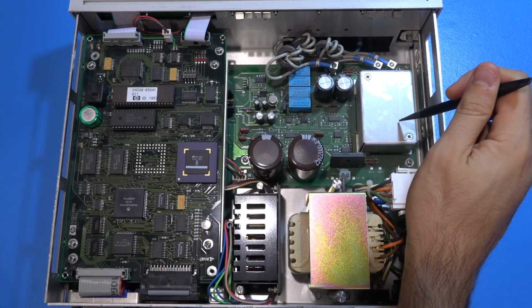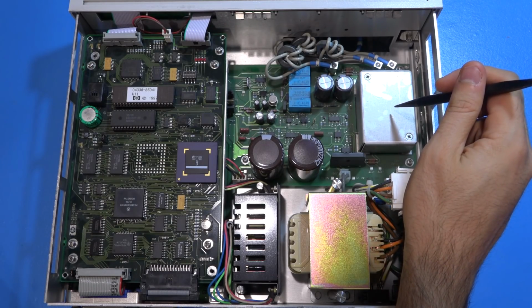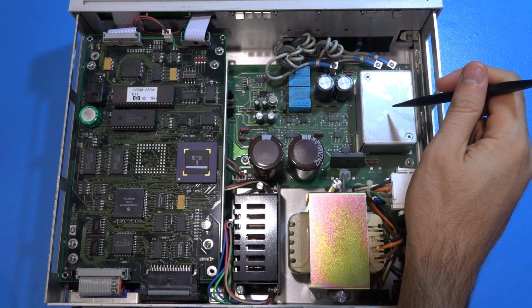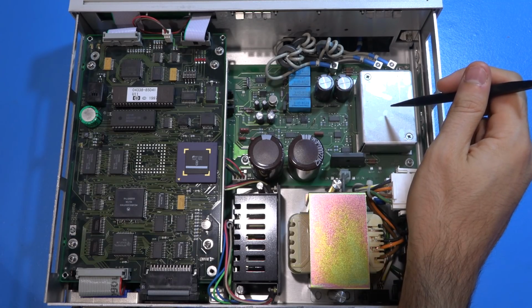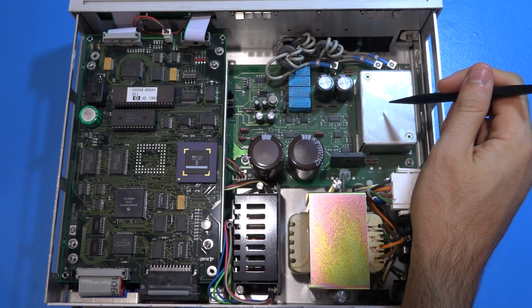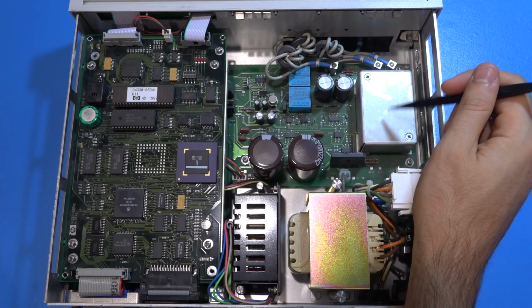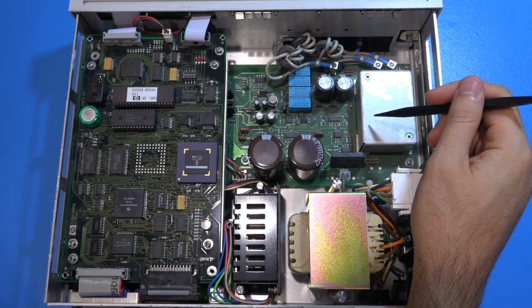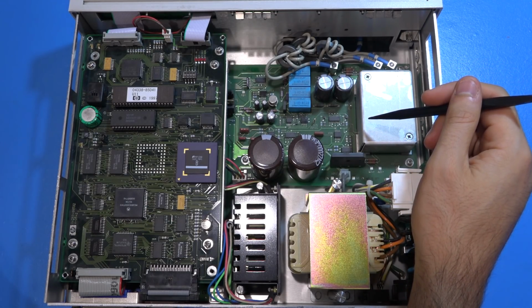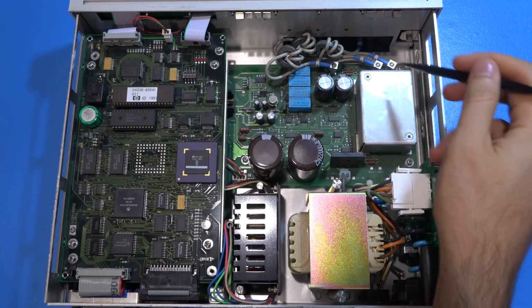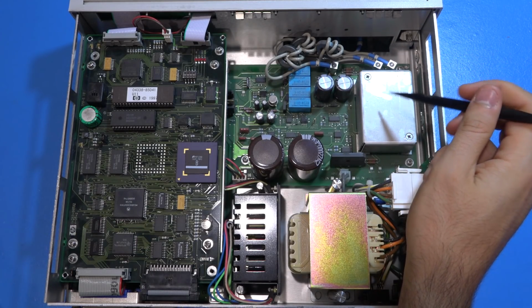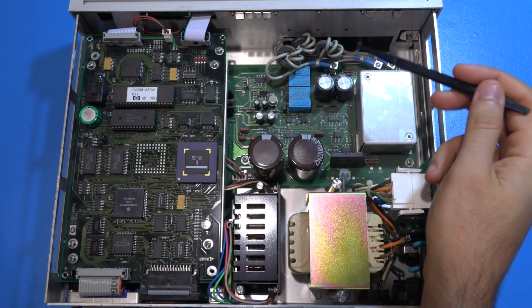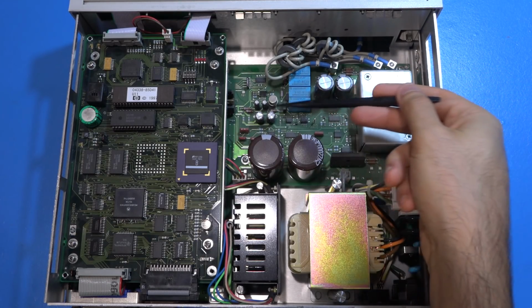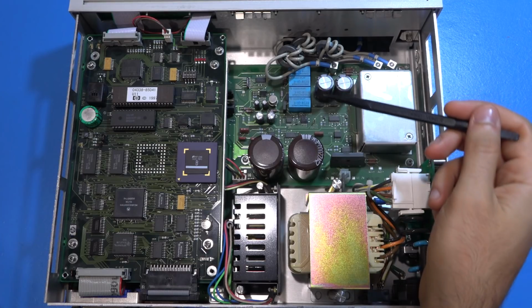Now here underneath this cage, we'll take a look at it probably. This is going to have our low noise amplifier front end. This is what is going to amplify the really, really small voltages or the currents that are required in order to capture exactly what resistance you are measuring. So it's going to have a part that's most likely long obsolete, but nonetheless, hopefully it still works. And once you amplify this, then you're going to have a very large signal, so then your SNR is not an issue after that. So this is a critical part for a noise issue from the front end. Relays may have perhaps to switch some range, and the rest of the circuits underneath this other board, and we'll have to take a look at that.